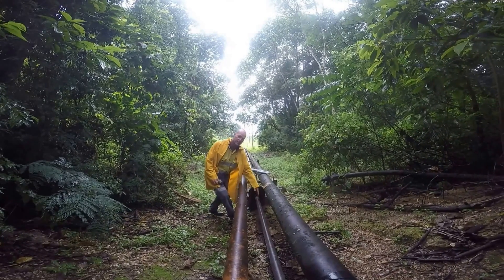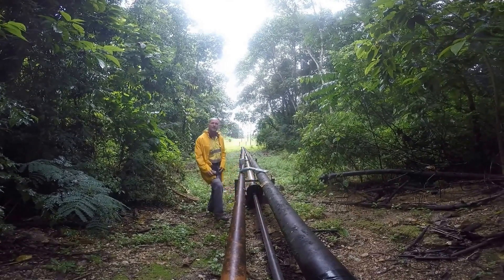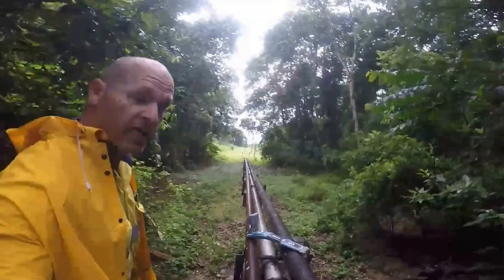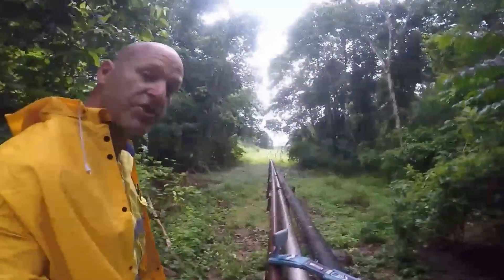The cable signal is going from this two inch line into this six inch line and we've been told there's some corrosion holes down the line. We should be able to get some good access to shine a camera in there with a torch and verify that there is a cable in there. We'll go for a walk in the six inch pipeline to find that corrosion point so we can shine a torch in.